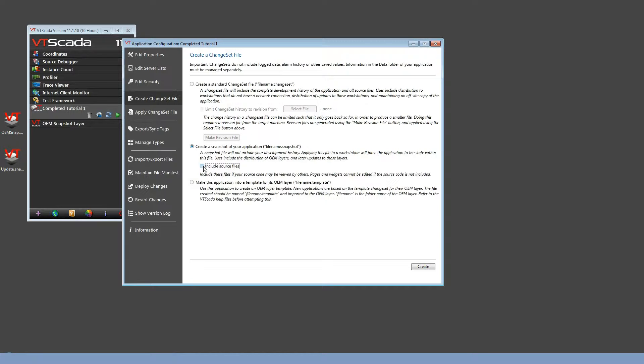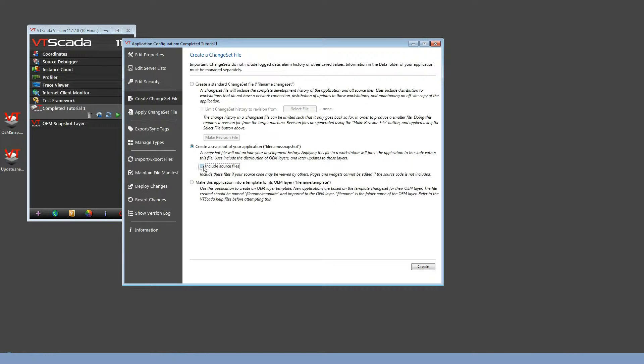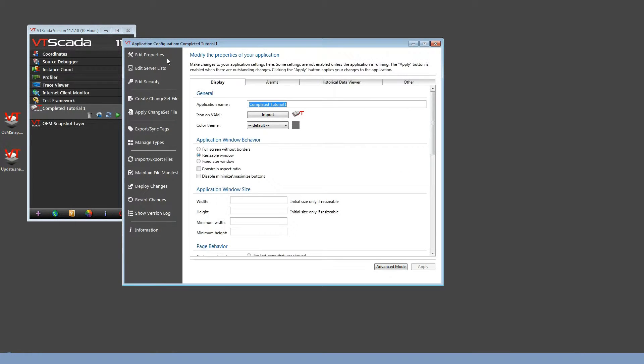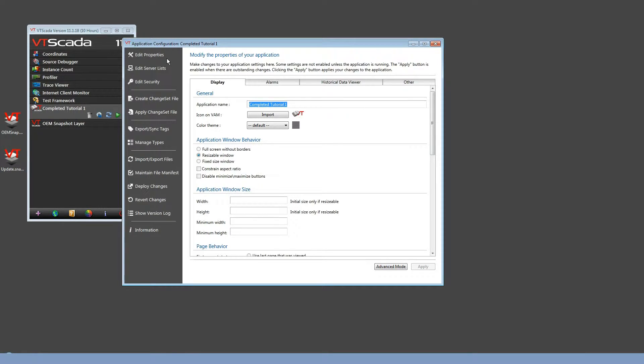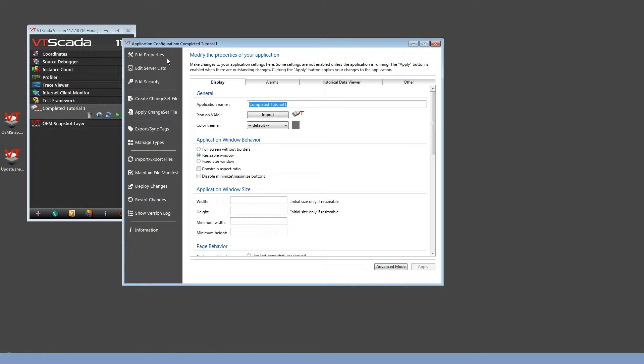To further protect the layer, you might do two things before creating the snapshot. Enable security, and also create a local copy of the application property 'do not start,' setting the value of that to 1. At the destination site, the layer can be activated and it can be used as an OEM layer, but it cannot be opened for editing, or if you did open it, no one would have security rights. And so this is, at least in part, how the VT SCADA layer works.